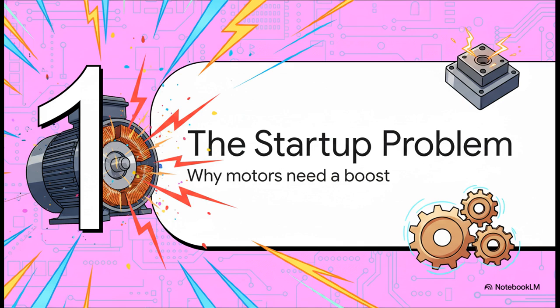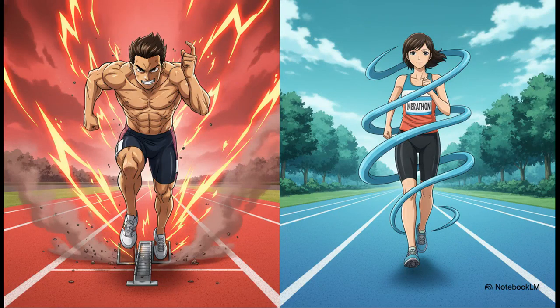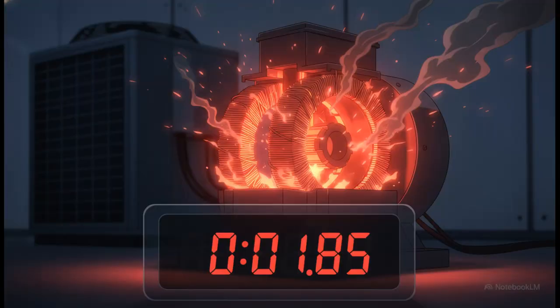Think about it. Getting a heavy motor spinning from a dead stop takes a huge initial burst of power. Now, inside the motor, you've got two different sets of wires, or windings, and they have totally different jobs. The start winding is like a sprinter. It's made of long, thin wire, which gives it high resistance and a ton of explosive torque to get things moving. But the run winding? That's your marathon runner. It's got thicker wire, lower resistance, and it's built to run efficiently all day long. And that sprinter? Well, he can't run a marathon. And this is the really critical part.